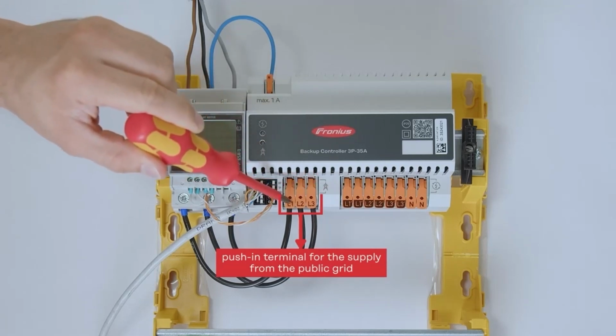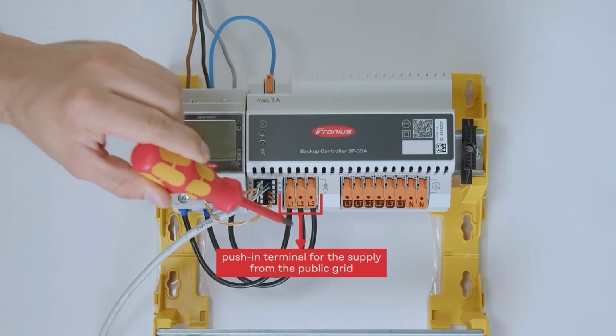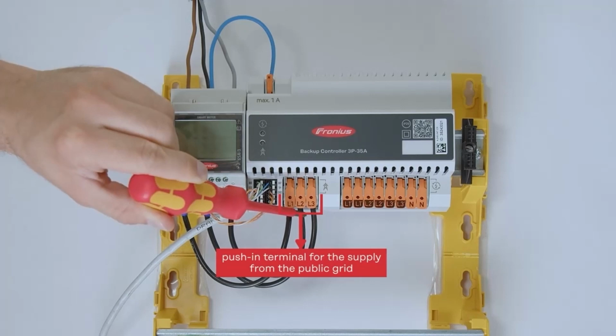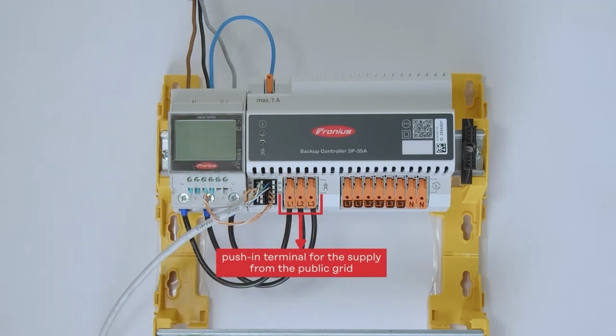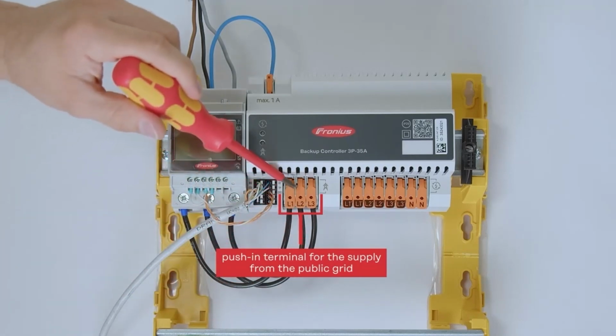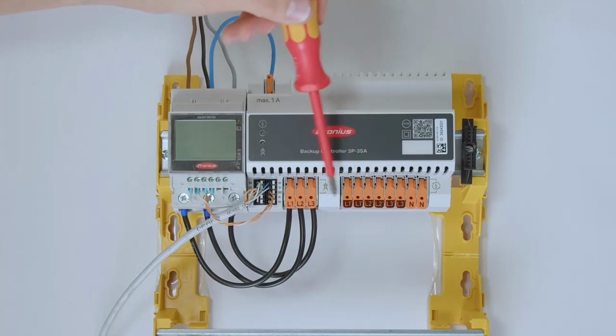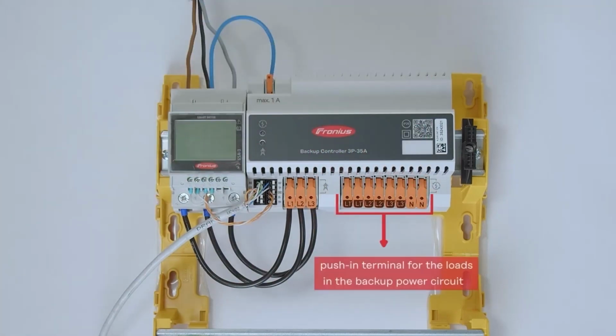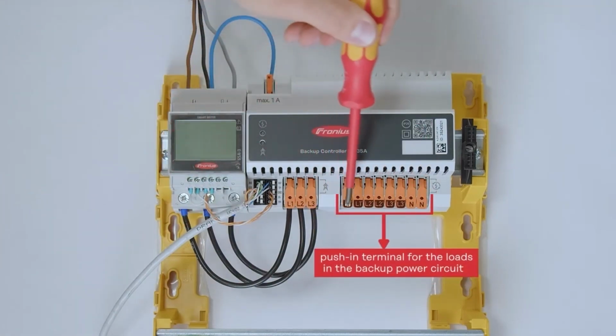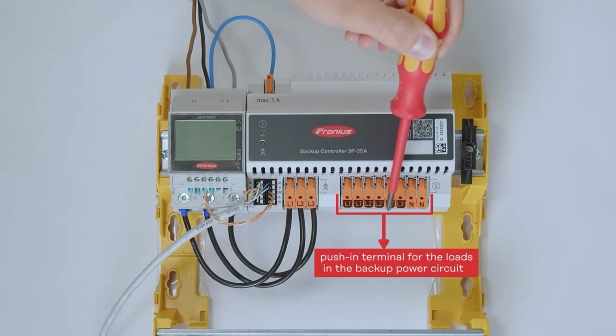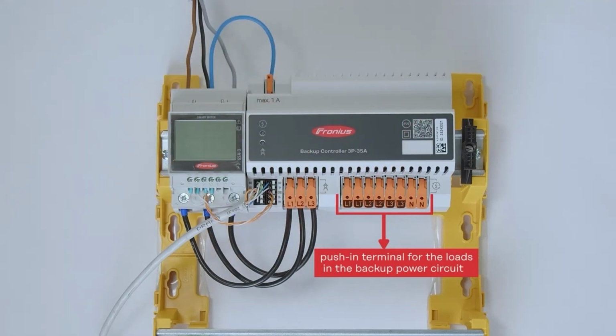So that means you have L1, 2 and 3 directly on the controller, where you can now cable your phases to the smart meter and back to the controller. On the right hand side we have now our backup loads, respective the household loads, and you see here you can now directly cable your household loads, your backup loads on the controller as well as the neutral conductor.